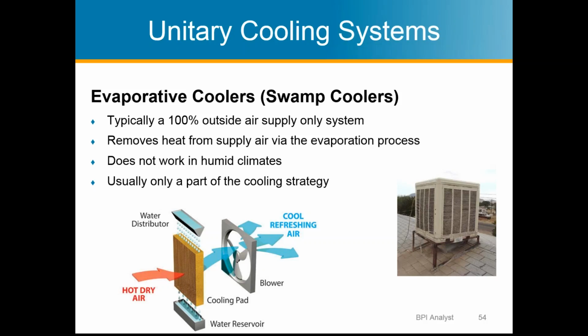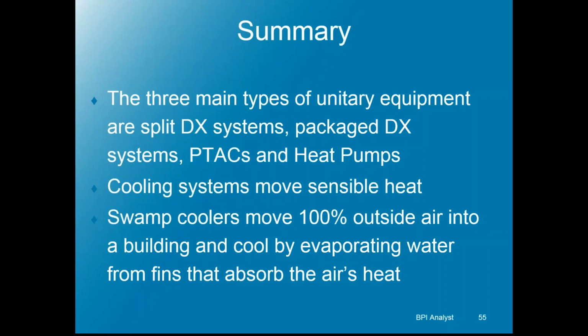And then just one slide on the evap coolers. You find them in residential, not all that often, but in some older existing buildings you're going to find them, and typically it uses 100% of the outside air. It blows the air across the moist wick, and that lowers the temperature. It's using some of the same principles of latent heat in that case, and then it blows it in. So it's using water to help cool the air before it enters the building. Obviously, it's pretty efficient. There's really only a pump and a fan energy happening here. Just not found all that often in existing residential anymore.